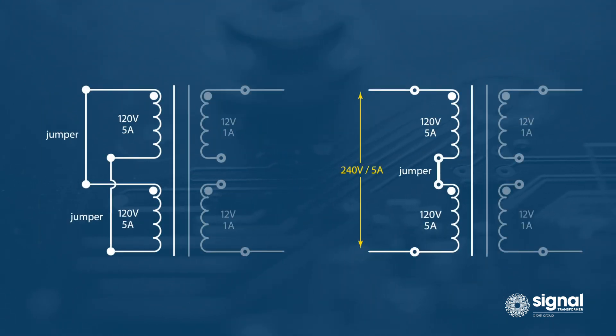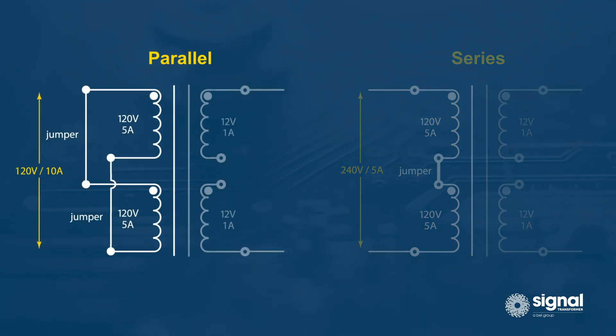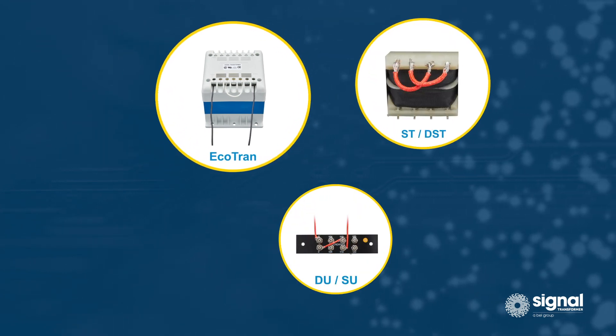These principles also apply to primary windings, meaning two 120-volt 5-amp primary windings can be wired in series for a 240-volt 5-amp input or in parallel for a 120-volt 10-amp input. Signal Transformer offers a wide range of transformers with multiple inputs and outputs.